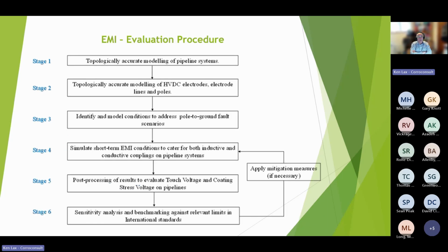This is the procedure we actually follow for the EMI assessment. There is mitigation that can be applied when the interference gets too high, because we have to recognize that with the best efforts of the designers and operators of the HVDC, there are times when you just can't reduce it anymore, and then we have to do something on the pipeline. We try to avoid that because, as operators of pipelines will know, digging down to a live pipeline is not a desirable task, and we try to avoid it wherever possible.